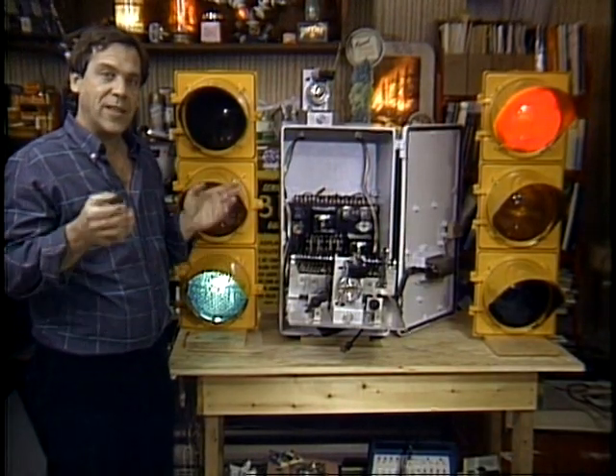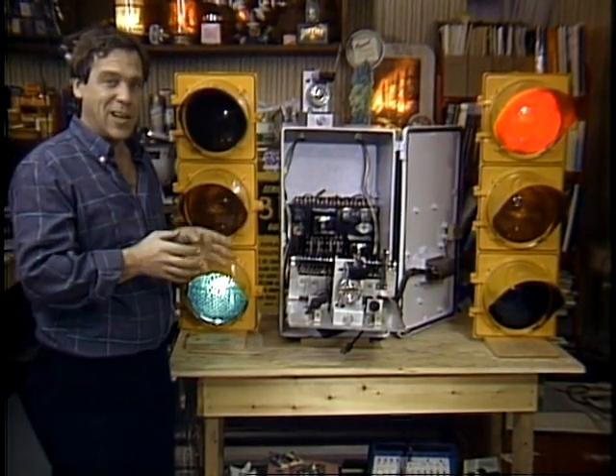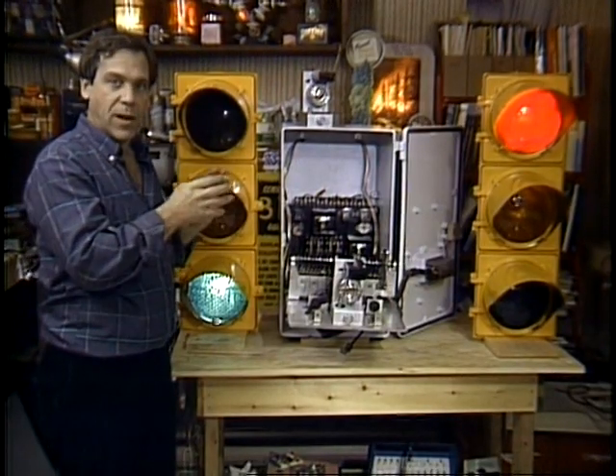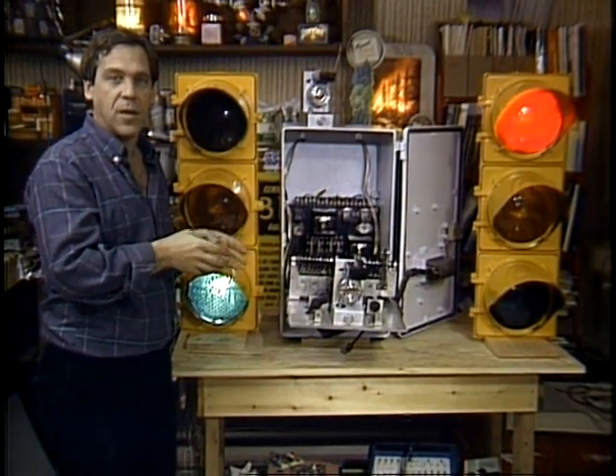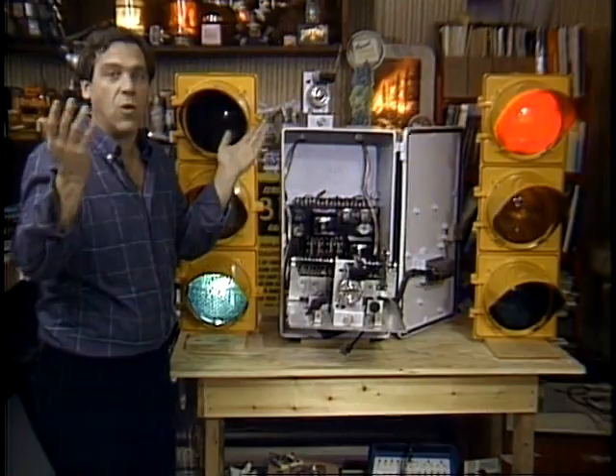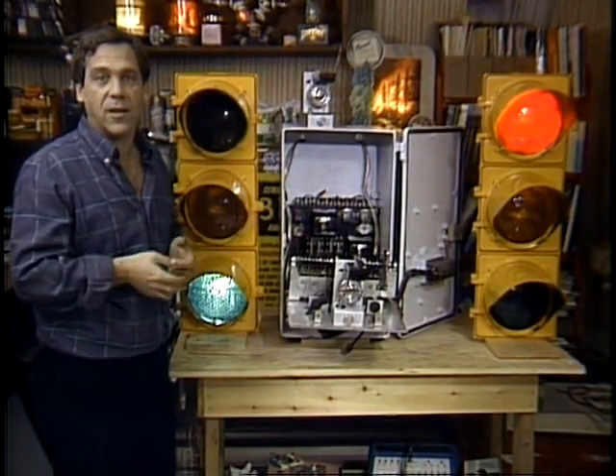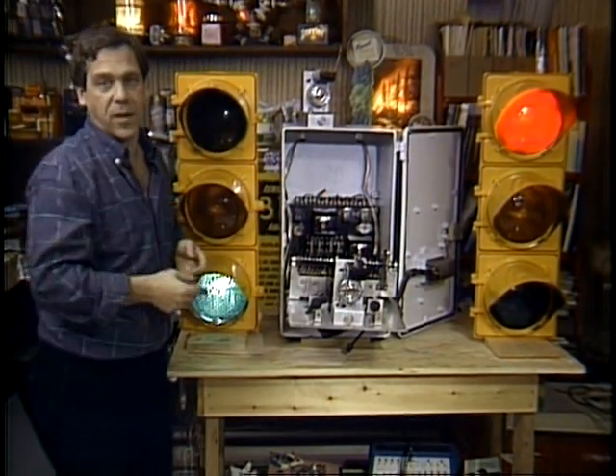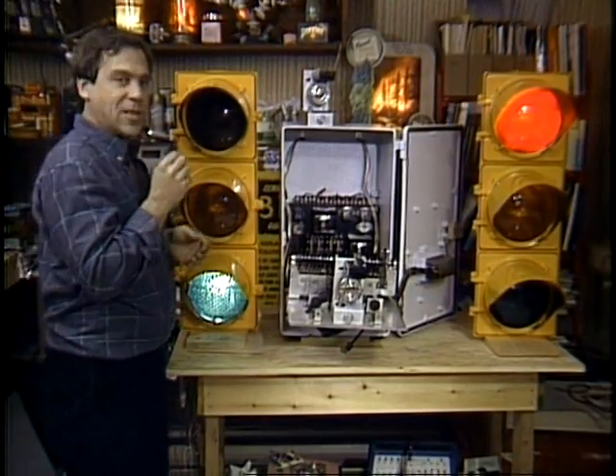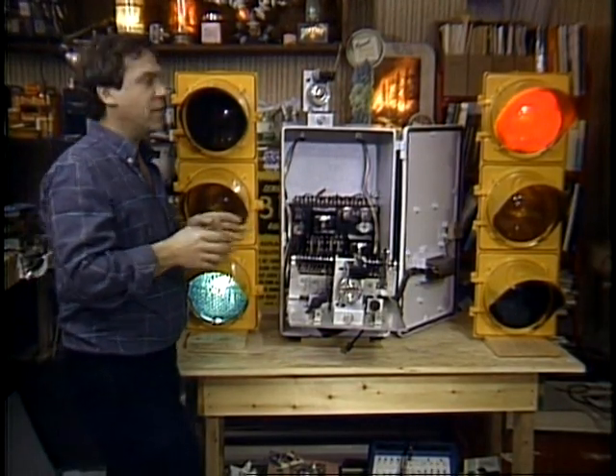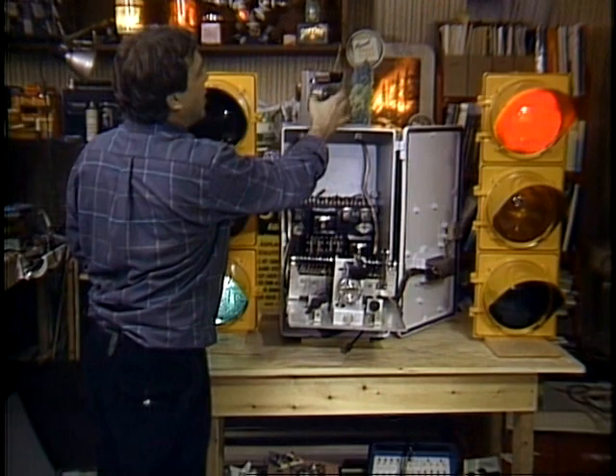Now, since the lights are on for different percentages of the time, the timing drum and the broken out cams on the shaft have to be in step. Otherwise, the controller might be holding Main Street yellow for 60% of the time, with everything else correspondingly mucked up. If that happens, the unit will stop on Main Street green and wait for this special key up here to come around.